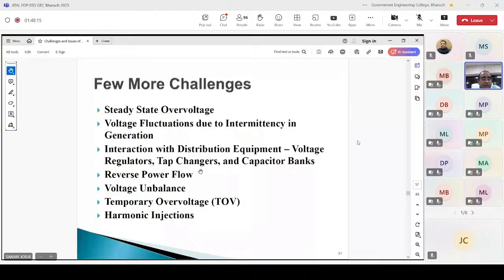Reverse power flow. This is a very big challenge and problem which has occurred due to the high level of penetration of REs, right? Conventionally, the lines had power flow only in one direction, right? But with the penetration and connection of RE, the power flow has become reverse also. That is creating problems for scheduling, forecasting as well as protection, right? Voltage unbalance is another challenge. Temporary over voltage is another technical issue.